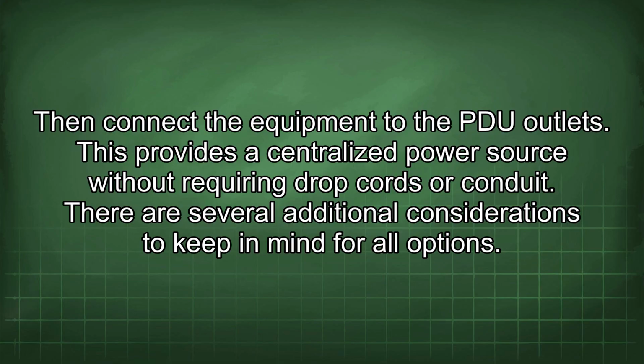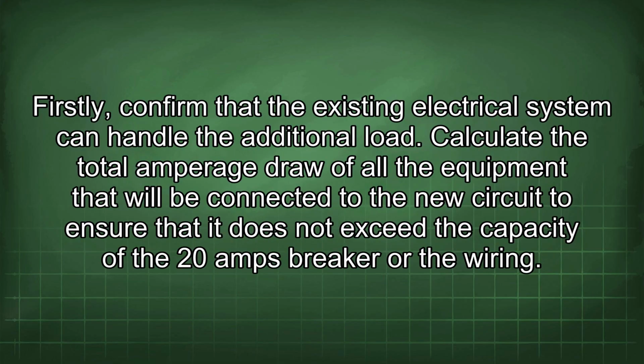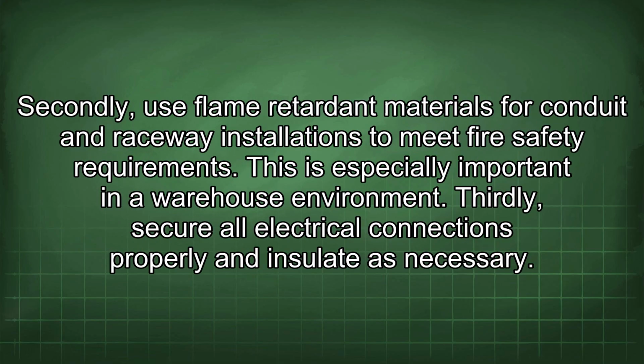There are several additional considerations to keep in mind for all options. Firstly, confirm that the existing electrical system can handle the additional load. Calculate the total amperage draw of all the equipment that will be connected to the new circuit to ensure that it does not exceed the capacity of the 20 amps breaker or the wiring. Secondly, use flame-retardant materials for conduit and raceway installations to meet fire safety requirements. This is especially important in a warehouse environment.